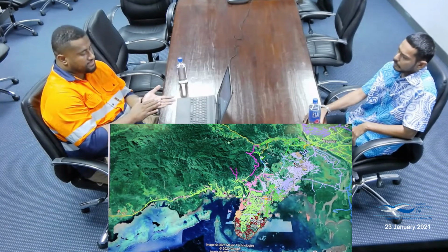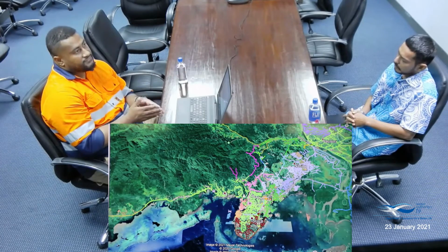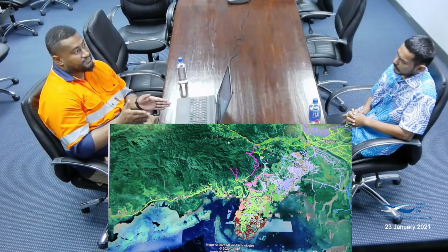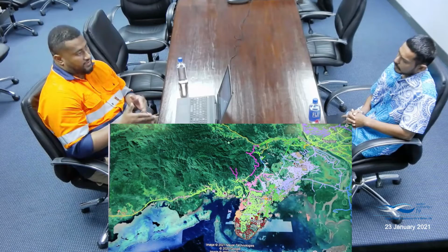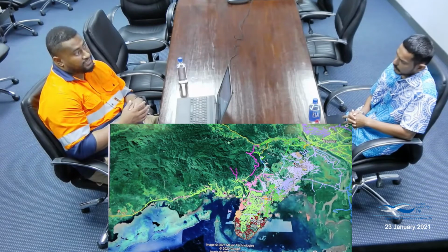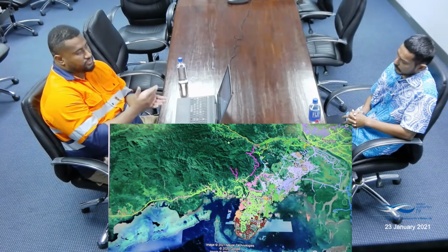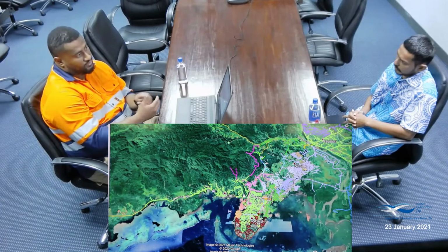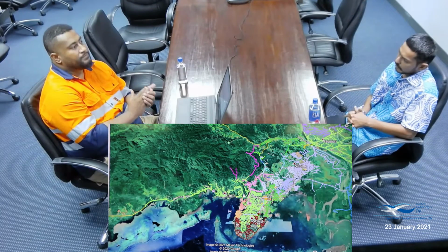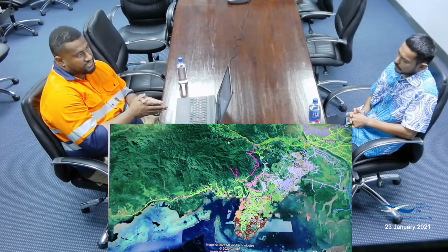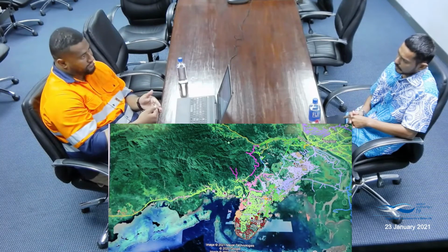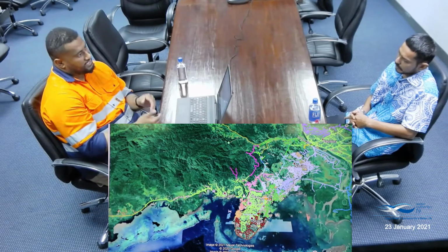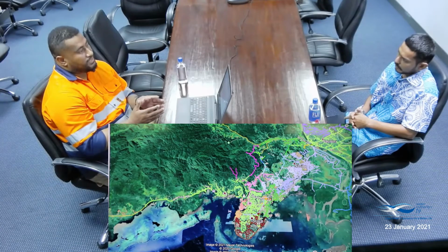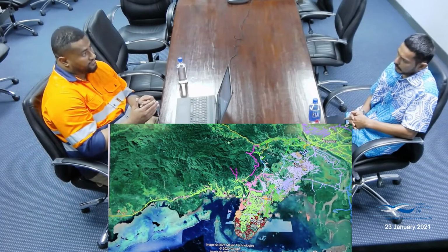The Tamavua Water Treatment Plant is designed to treat 60 million liters. We're pushing it to 65, and right now we're pushing it to about 75 million liters. So it's producing over its design capacity at the moment. That's why when it rains we face production issues, because we then have to revert the plant back to its design capacity of 60 million liters, since it can only safely treat water up to that level when turbidity goes up.